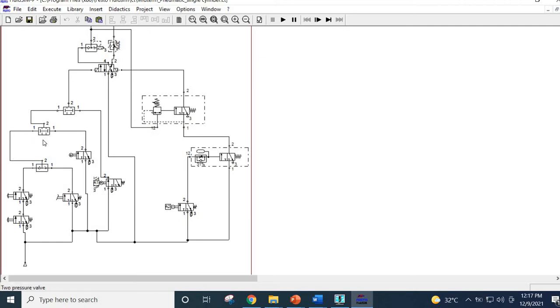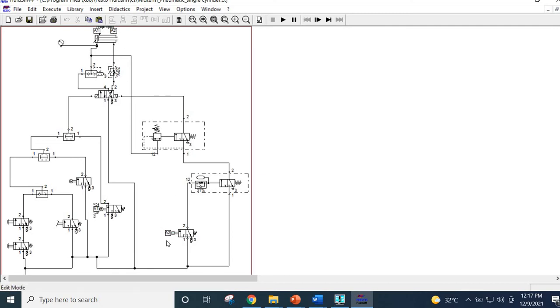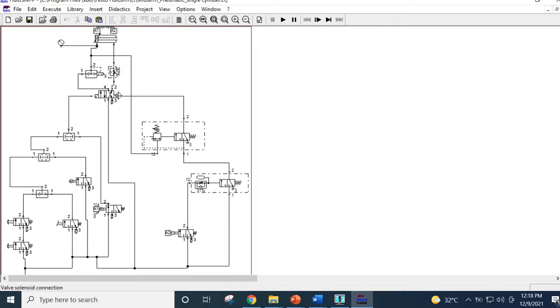We have two push buttons — either you press the two push buttons or the foot pedal valve — so there is a shuttle valve here. The output of the shuttle valve goes to an AND condition, which may be the part detector. There is another AND condition that the cylinder must be in its initial position. All these conditions cause the cylinder to move forward, with controllable speed due to the one-way flow control valve. It should retract after reaching the retraction position, which is why you have the A2 limit switch. This initiates the timer, and the timer also ensures that the pressure at the chamber reaches a certain level before the air causes the valve to switch direction and retract. Retraction is as fast as possible due to the quick exhaust valve.